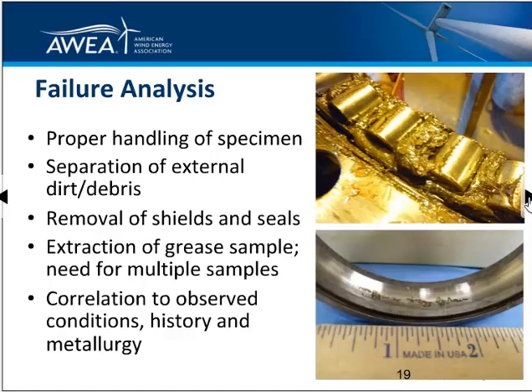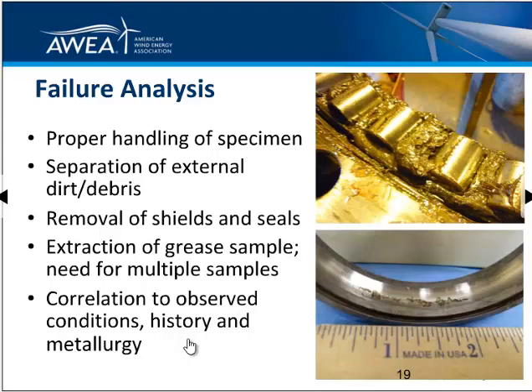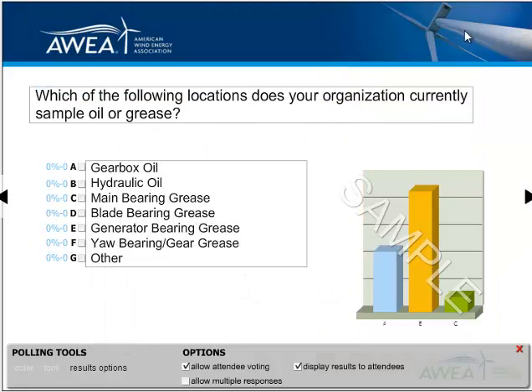The ASTM standard also talks about failure analysis. When there is a failure, there is a lot of value in extracting information about the factors that led to it. It talks about proper handling of the specimen, keeping it clean and protected, separating external dirt and debris from the grease that was in the bearing, how we remove shields and seals to access the location, the need for multiple samples to see different things going on, and correlating observed conditions to history and metallurgy in the failure analysis.